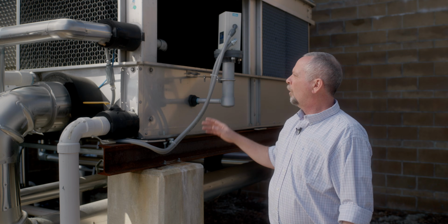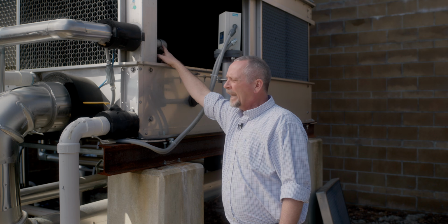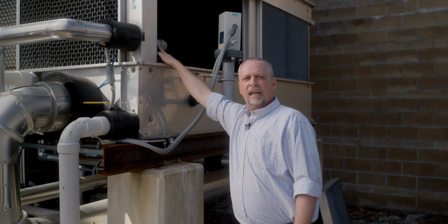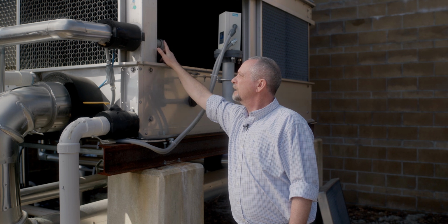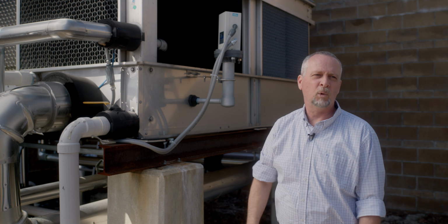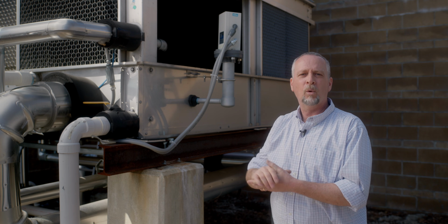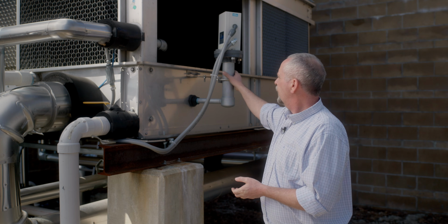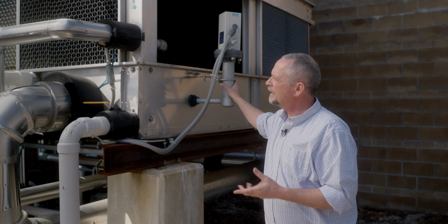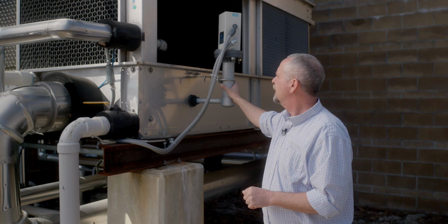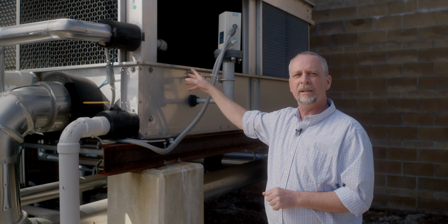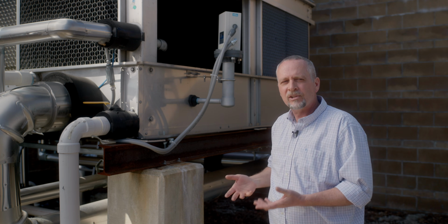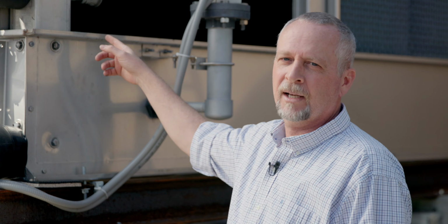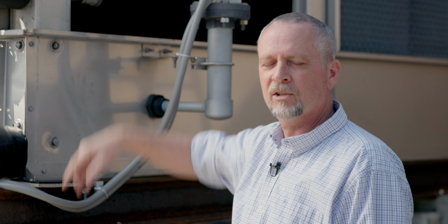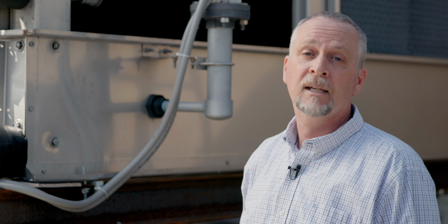One thing to be cognizant of on a manual float valve, you have to have a pressure regulating valve in front of it. You can't hit these manual float valves with more than 45 psi of water pressure, or it'll cause the valve to leak. You got a little more grace on these electronic ones. I think that solenoid will take up to 90 to 100 psi, somewhere in that range. But if you've got a manual float and you see it's always leaking by, and you can lift the float up, it still doesn't stop leaking by, more than likely the valve's defective because you've been hitting it with too much water pressure. That's when you go back and trace the water line back into the building and try to find if they have a PRV installed or not.